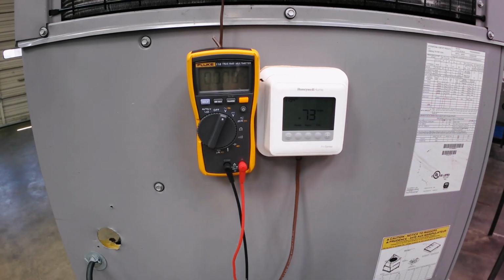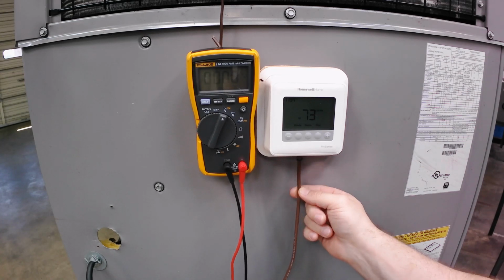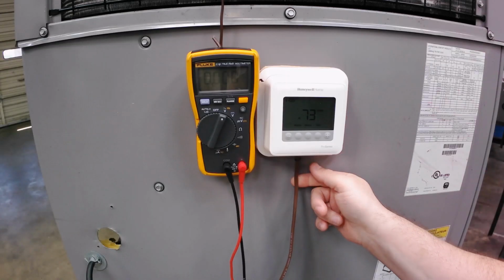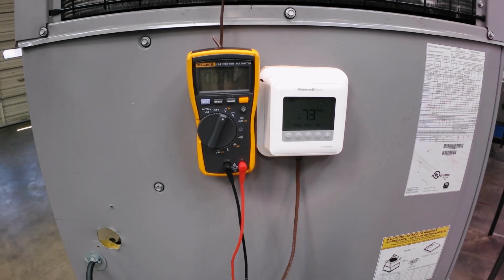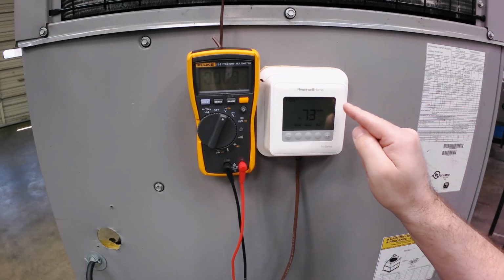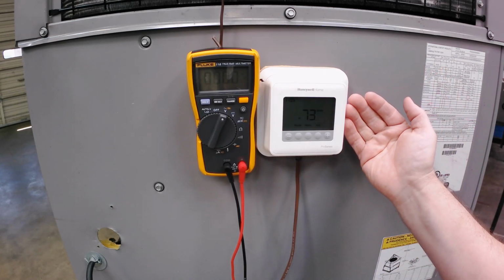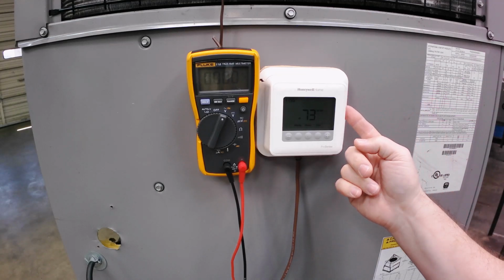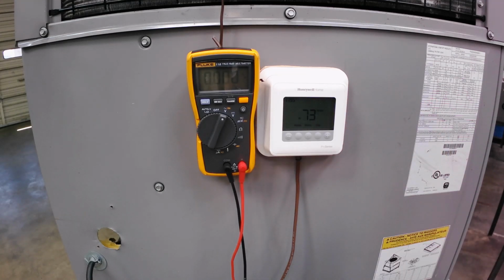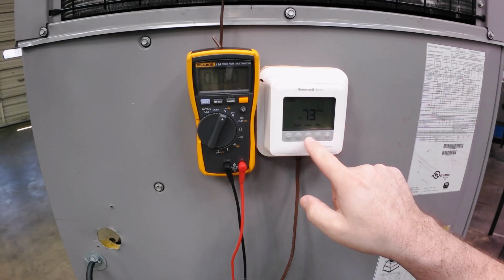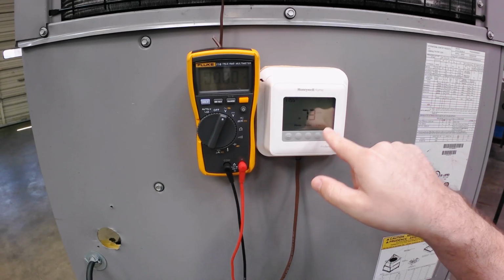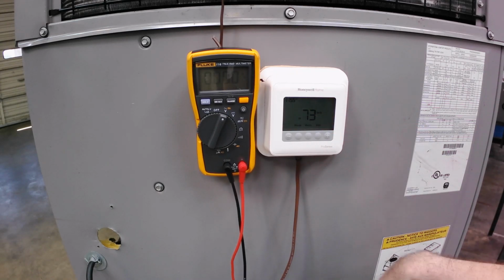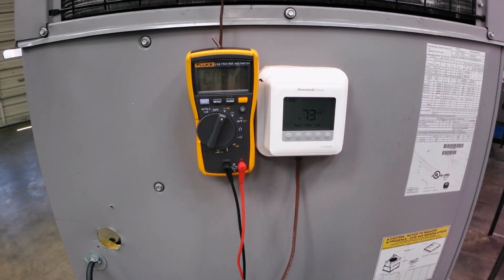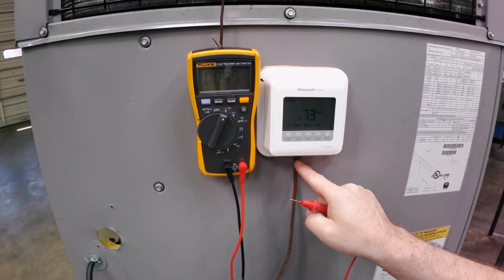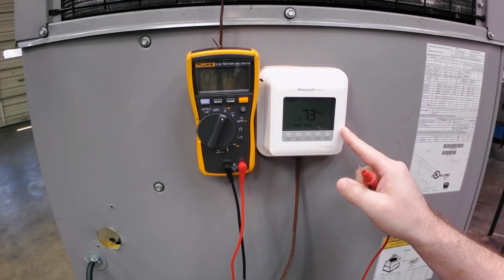And now we should go check at the other end of this wire. It's going to be at the air handler, it's going to be at the outdoor unit, it's going to be, in this case, right up, 2 feet away, going into the service side of the package unit. But the R on this end has the power to make something work. What you need to do is go to the other end and make sure that it gets there. Okay, so I'm going to turn the fan from auto to on, and we're going to go right across the corner here, and we're going to check from G to common. Everything that you need to check, right?